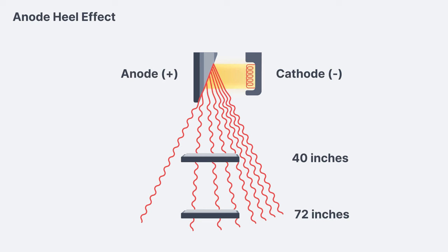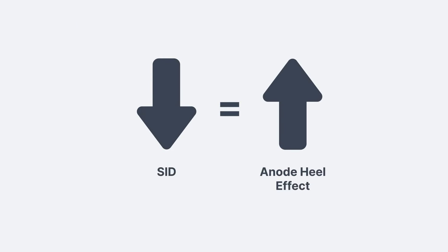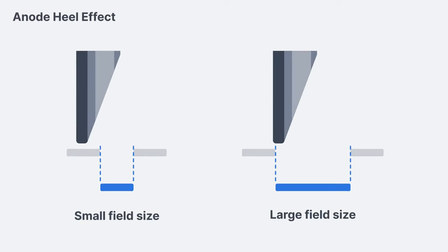Changes in SID also affect the extent of the anode heel effect. Decreasing or shortening the SID increases the heel effect. Shortening the distance causes the receptor to get exposed to more of the low intensity beam on the anode side and more of the high intensity beam on the cathode side. There is an increased difference in intensity, which is the same as saying there is an increased anode heel effect. The relationship between SID and the heel effect is inverse — as the SID decreases, the anode heel effect increases.